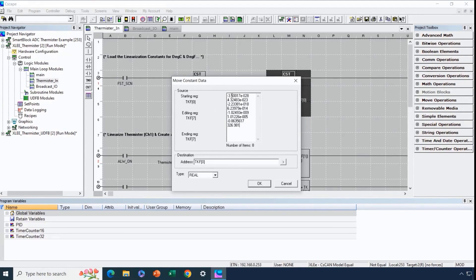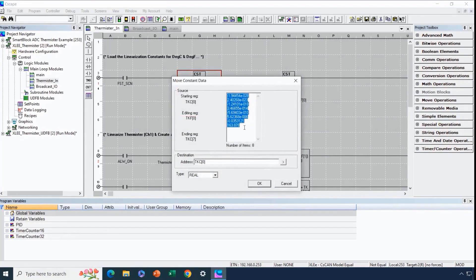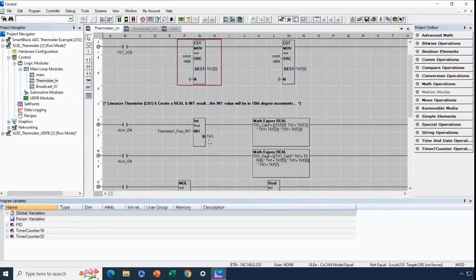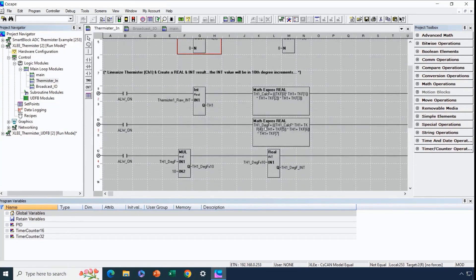The array holds eight different values from TKF0 through TKF7 — the variable name stands for thermistor constant for Fahrenheit. If doing the conversion in degrees Celsius, we could use a separate set of coefficients aimed towards degrees Celsius, and we created a different real array of dimension eight for thermistor constants in degrees Celsius. We're using degrees Fahrenheit in this application. We've taken those coefficients and the raw value coming in through the analog input register and run it through the calculation in two steps. At the end, we have a real value in degrees Fahrenheit and also created an integer value in tenth-degree increments by multiplying the real value by 10 and converting from real to integer.